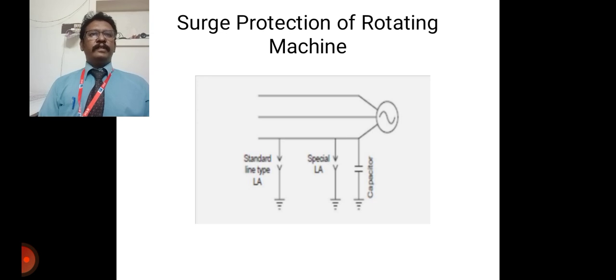The main difference between the winding of a rotating machine and the transformer is that in case of a rotating machine, the turns are fewer but longer, and are deeply buried into the stator slots. Surge impedance of a rotating machine is approximately 1K, that is 1000 ohms. And since the inductance and capacitance of windings are large as compared to the overhead lines, the velocity of propagation is lower than that of the lines. For analytical purposes, for the machine it is 15 to 20 meters per microsecond.